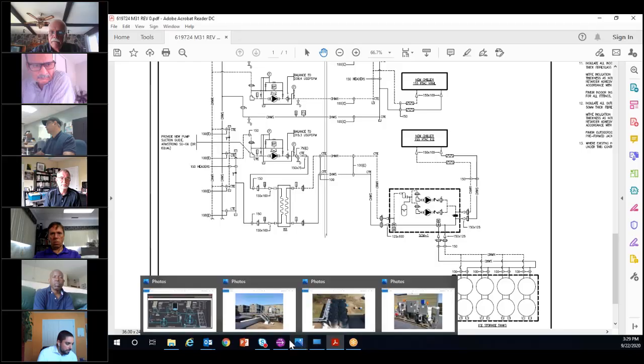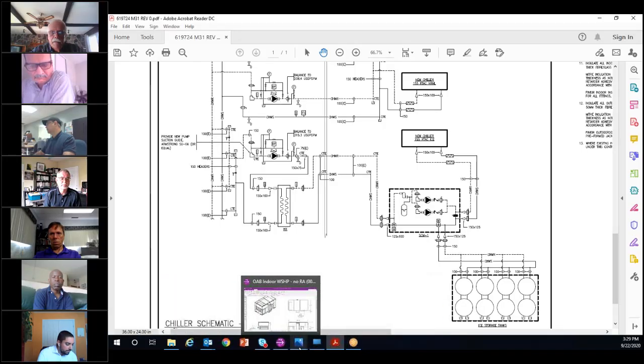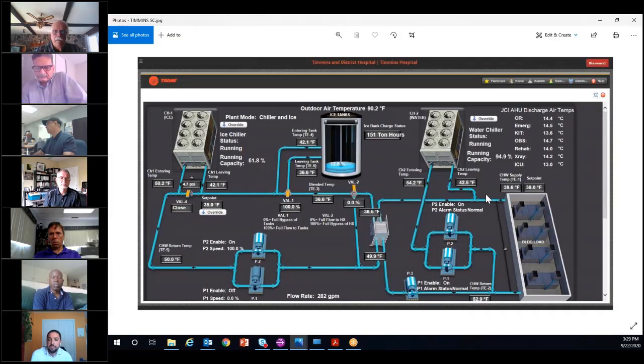So let's see, I'm throwing up another slide picture here. This is a picture of just the BAS interface operator screen that we provided on this project. Controls optimization was certainly a big piece of this as well. This shows a nice visual schematic of what the system looks like in terms of having your chiller and your ice tank and your pump on the glycol side with your heat exchanger. So you can essentially treat this as one big chiller in parallel with your water chiller, providing your cooling to the building. And as part of the controls, we are monitoring the discharge air temperature from the air handlers for all of the critical zones that the hospital is concerned about over here on the top right corner.